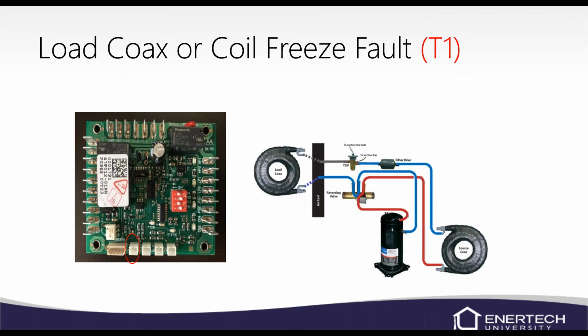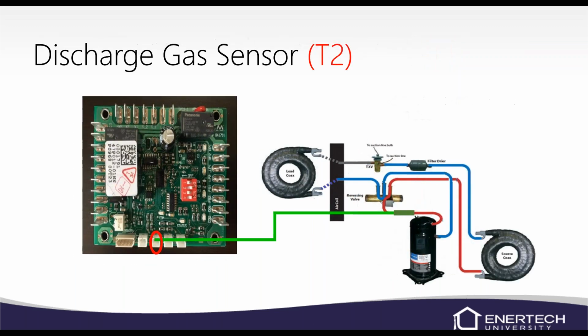A load coax or a coil freeze fault will look at your T1 sensor, and that's located on the line in between your load heat exchanger and your expansion device. So if it sees that load coil is below 30 degrees for more than 30 seconds, it'll open up that switch. A lot of times that's caused by an airflow issue, or if it's a water-to-water unit, a load water flow problem.